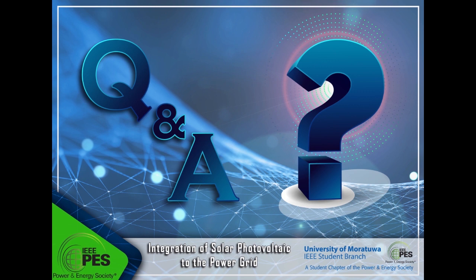Theoretically, it's possible, because the converter has slow outer loop controls and fast inner loop controls. Slow outer loop controls can contribute to low frequency oscillations against other dynamic devices in the network, so this is theoretically possible. I don't remember coming across any industry or utility experiences of low frequency oscillations between inverters and the grid, but as I said, theoretically it's possible because converters have slow controllers in the outer loops.